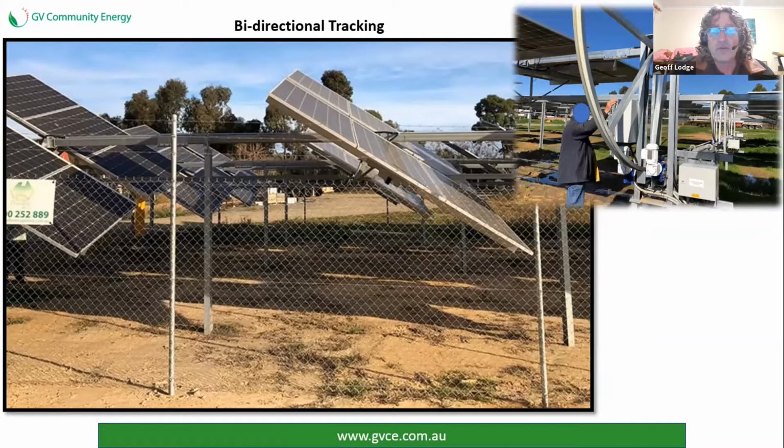And this photo is looking south, so the panels are currently facing west. And you can see it's late in the day. You do have some shading on those panels. Had there been more space between it, you would have taken more advantage of that. But late in the afternoon, it's not critical. But the other piece of infrastructure, in this case, you've got a security fence in addition to the ground mounting equipment.